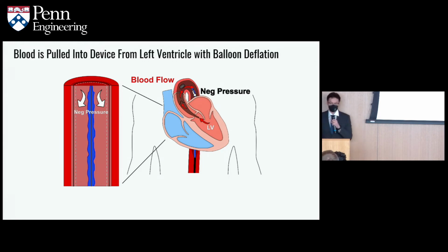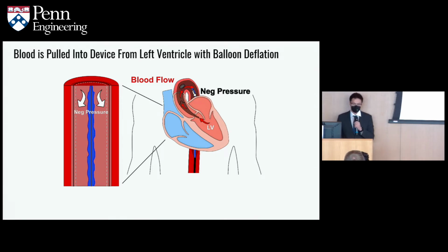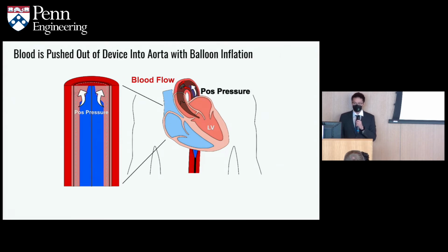Thank you, Francesca. So now that everything is in position, the balloon is ready to start pumping blood. When the balloon deflates, this creates negative pressure inside the sheath of our device, which pulls blood from the left ventricle through a one-way valve into the sheath of our device. And when the balloon later inflates, this positive pressure that's now inside the sheath pushes blood out of another one-way valve into the aorta, where the blood travels to the rest of the body.